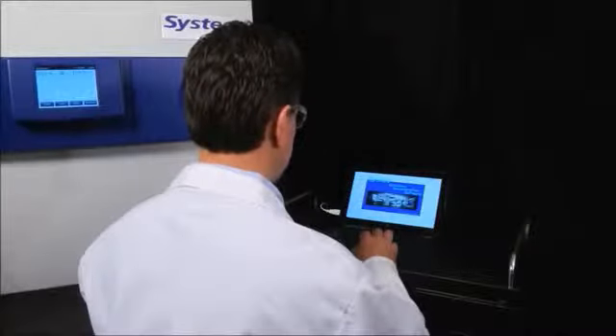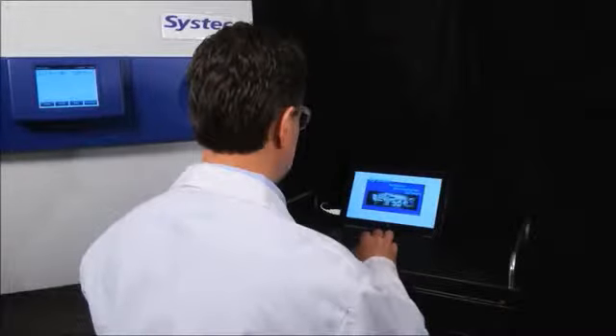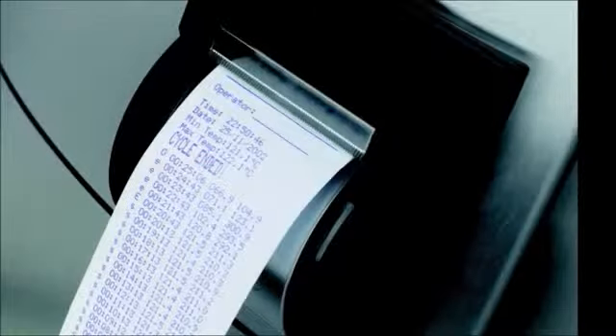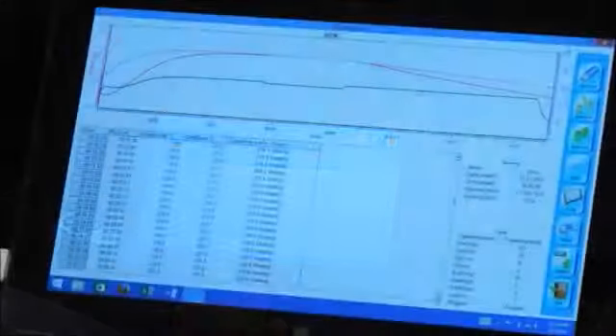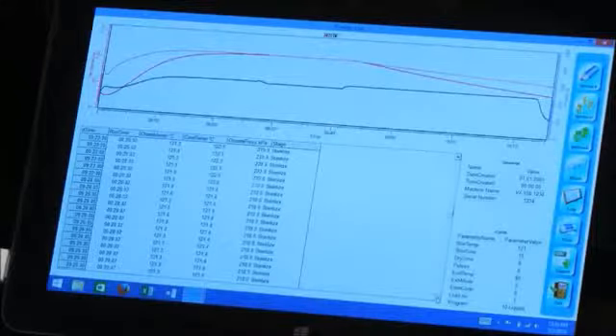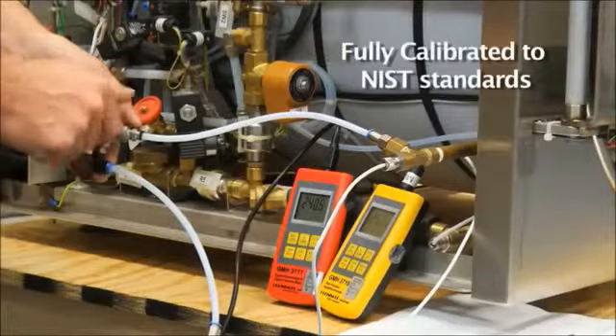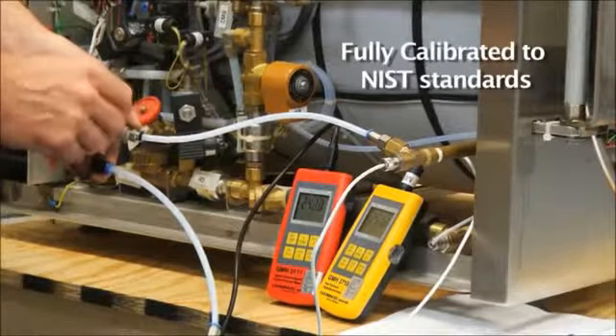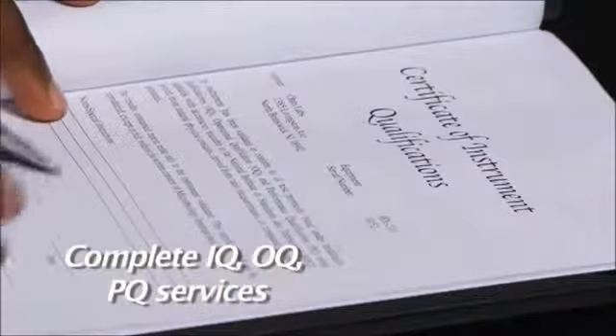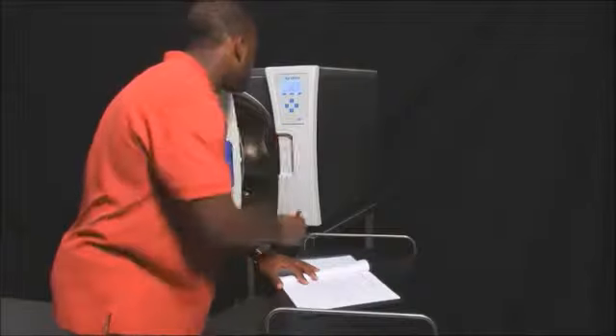For quality control and documentation purposes, cycle information can be recorded via ticket printer or directly to a computer using our ADS software. Information on time, temperature, and pressure can be stored for each cycle run with an array of numerical and graphical display options. All Systec autoclaves are delivered fully calibrated to NIST standards for pressure and temperature. We do have the documentation available. We also offer installation specifications to the end user prior to the install.